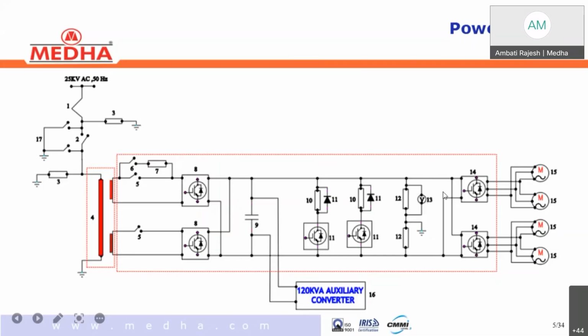And further, pure DC, after this brake chopper and ELD, will be given to two traction converters. Both of these are IGBT based traction converters. These converters convert DC into three-phase AC as per the computer commands. This output we call VVVF, variable voltage variable frequency output. The voltage and frequency both can vary as per the requirement, either voltage or frequency or both. This voltage varies from 0 to 1430 volts and frequency varies from 0 to 160 hertz.